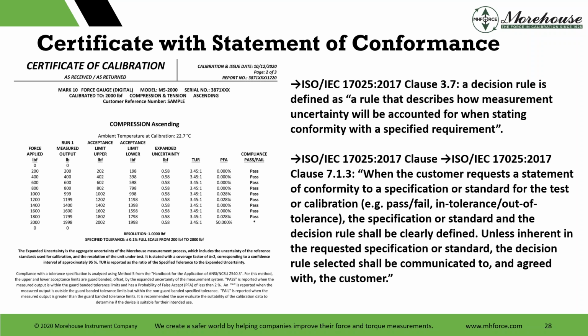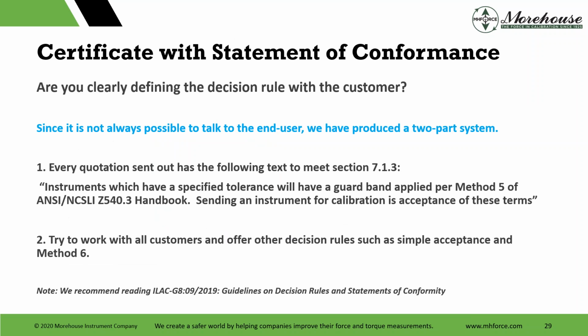Here is an example, and this is taken from the handbook ANSI/NCSLI Z540, and we're using method 5 here. But we're going to talk about this some more. We're reporting expanded uncertainty, we're reporting TUR, PFA, and then compliance rules. And we're doing it to method 5. Did the customer agree to that? So, are you clearly defining the decision rule with the customer?